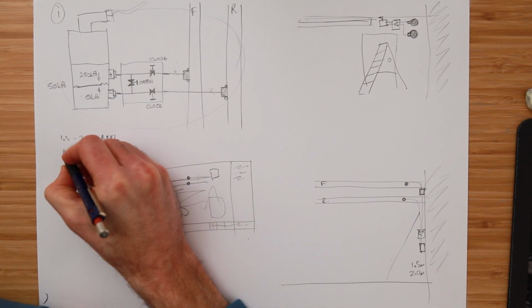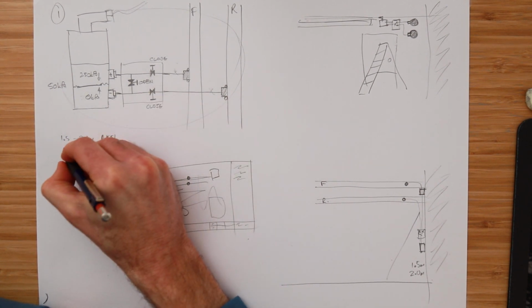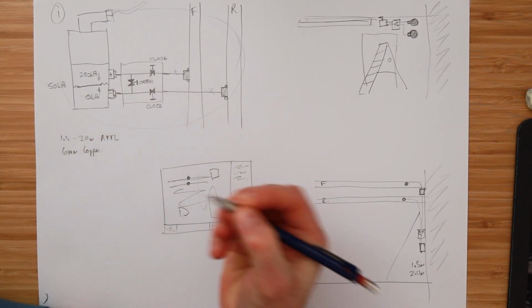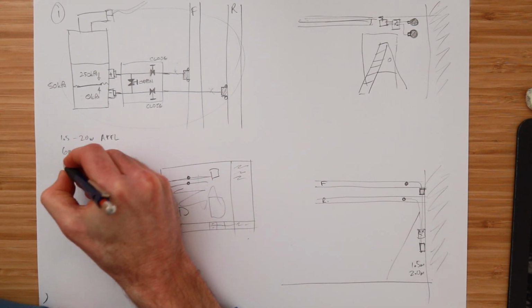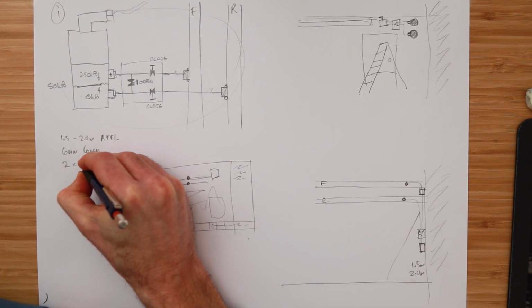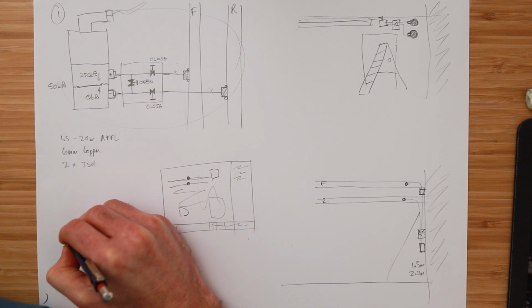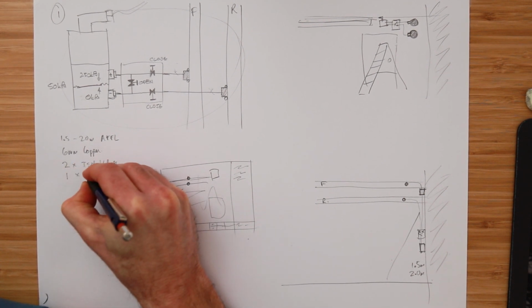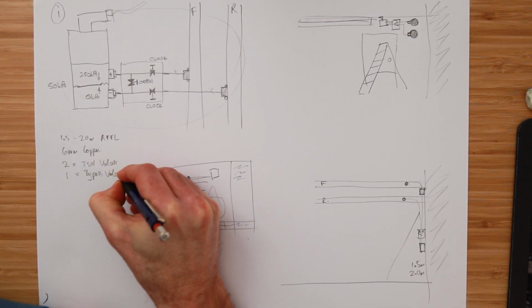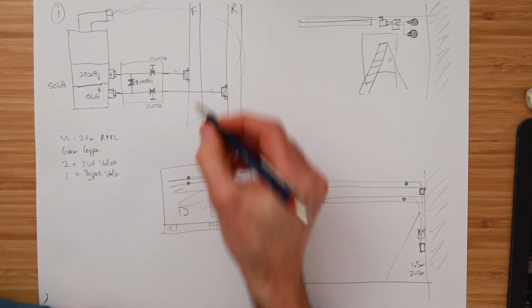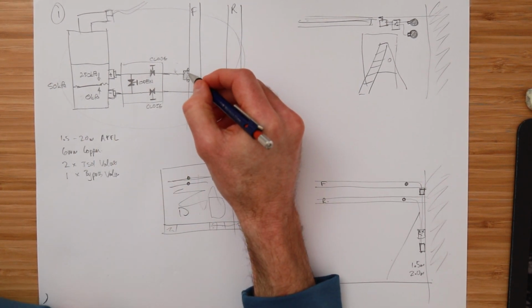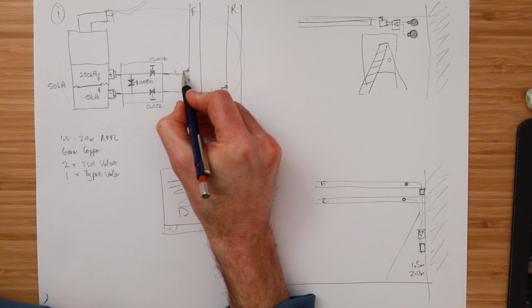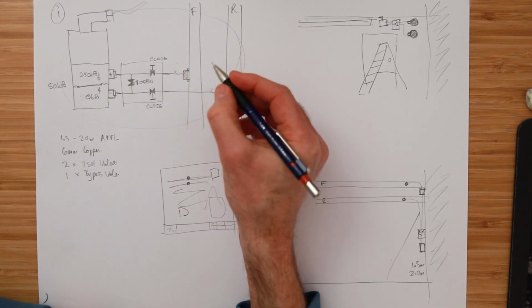Maybe you tell them that this pipe needs to be 6mm copper. You tell them that you need a manifold with 2 little isolation valves and 1 bypass valve. You tell them that in the sheet. I think in the UK and here in Australia, this is a 1/2 inch British standard pipe.